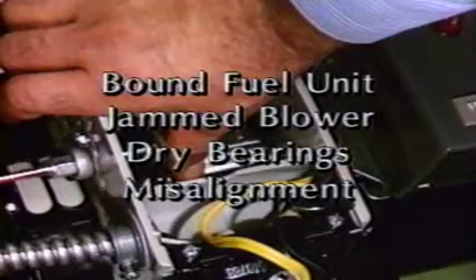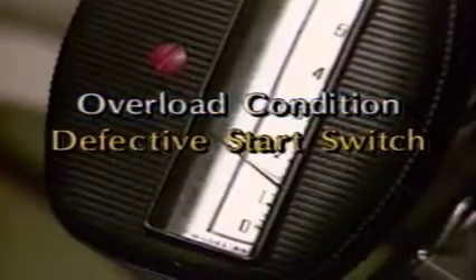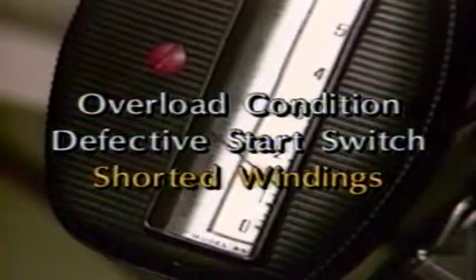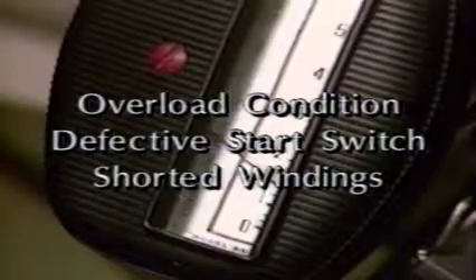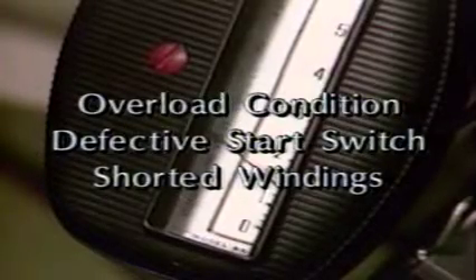Other motor conditions that can cause burner shutdown include excessive amperage draw. Check for this by starting the motor, attaching the amp probe, and reading the current draw. If it's more than 10% of the rating on the nameplate, you have an overload condition, a defective start switch, or shorted windings. Generally, you may not be able to correct these conditions in the field. Therefore, replace the motor.